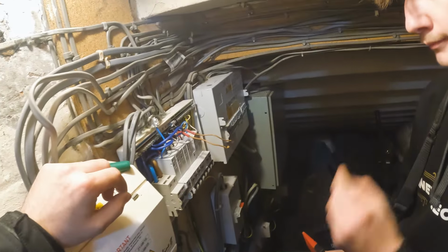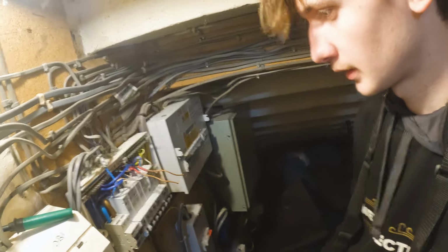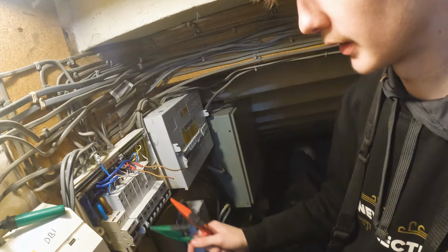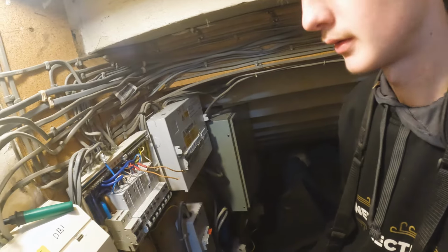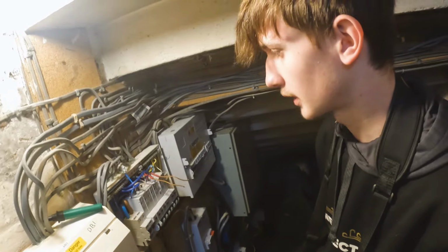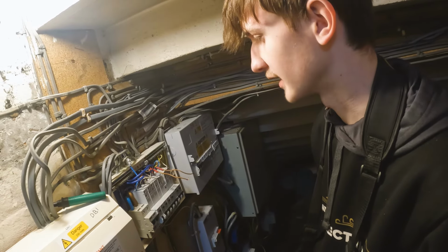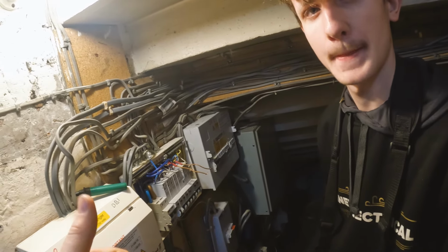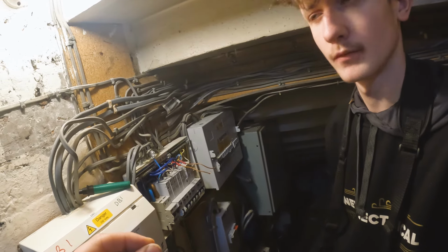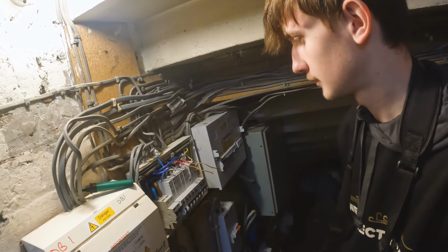Right then, so we've got the circuit here, it's protected by an RCBO. What three functions has that got then? You've got your overcurrent. What's that then? So this breaker's maximum is 10 amp, so anything over 10 amp it'll trip. That's overcurrent, nice. And then what else have we got? Short circuit. So when does that happen in this scenario? A low resistance. So like when live touches earth or neutral, it creates a low resistance, therefore creating a high current, and then it trips.